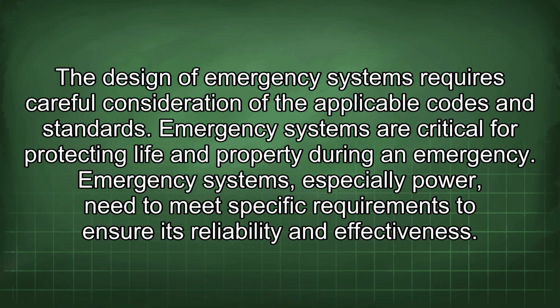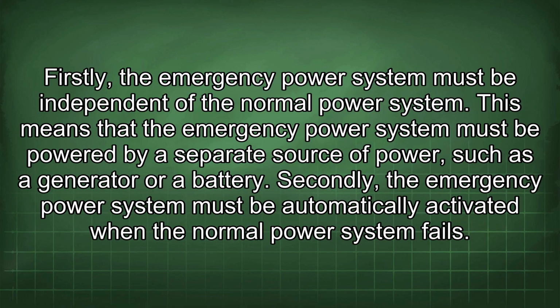Emergency systems are critical for protecting life and property during an emergency. Emergency systems, especially power, need to meet specific requirements to ensure their reliability and effectiveness. Firstly, the emergency power system must be independent of the normal power system. This means that the emergency power system must be powered by a separate source of power, such as a generator or a battery.